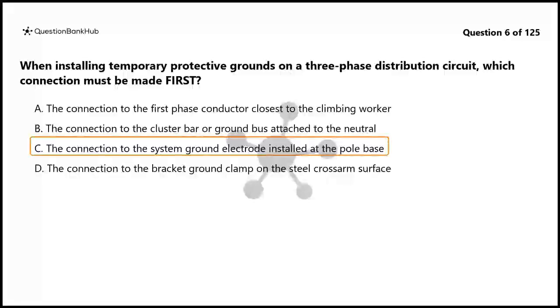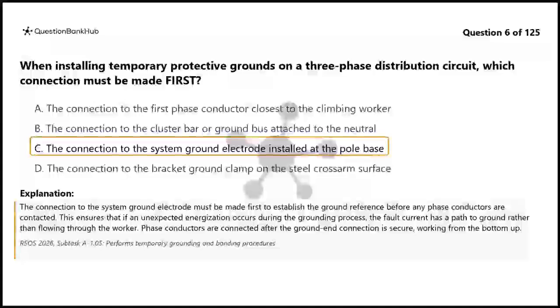The correct answer is C. The connection to the system ground electrode must be made first to establish the ground reference before any phase conductors are contacted. This ensures that if an unexpected energization occurs during the grounding process, the fault current has a path to ground rather than flowing through the worker. Phase conductors are connected after the ground end connection is secure, working from the bottom up.